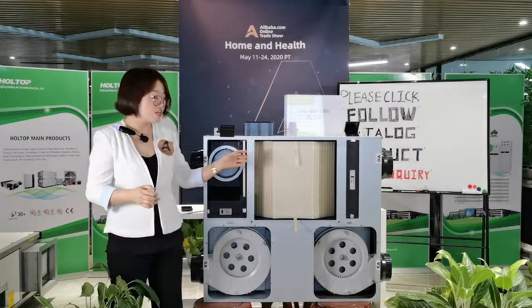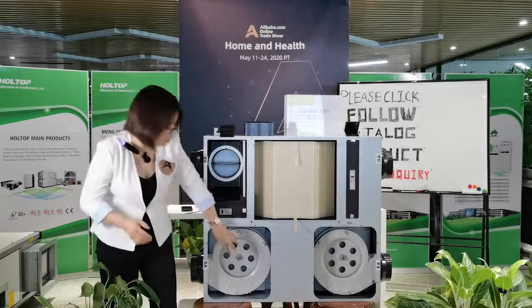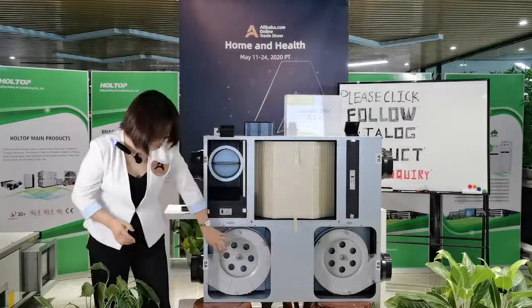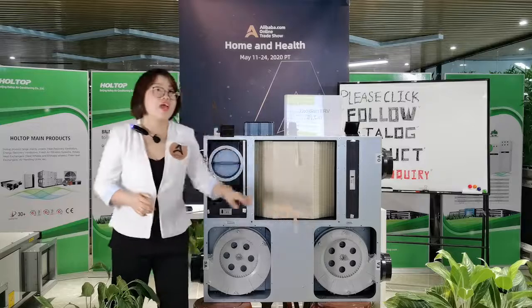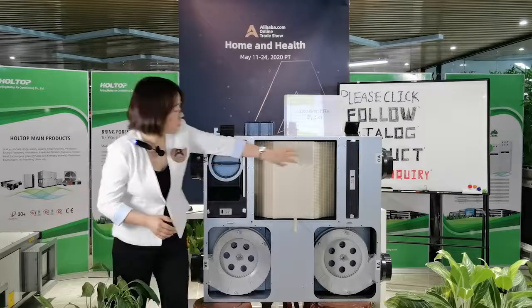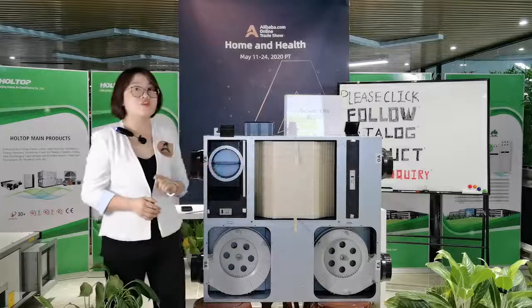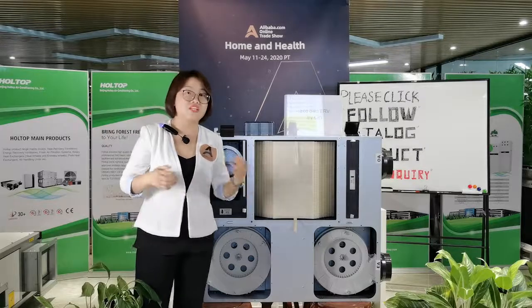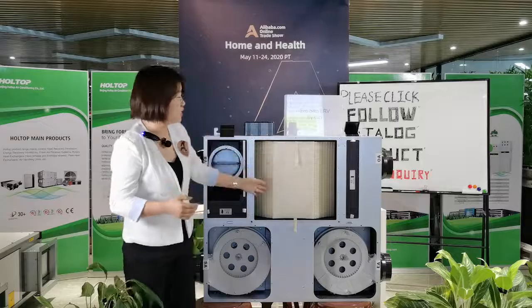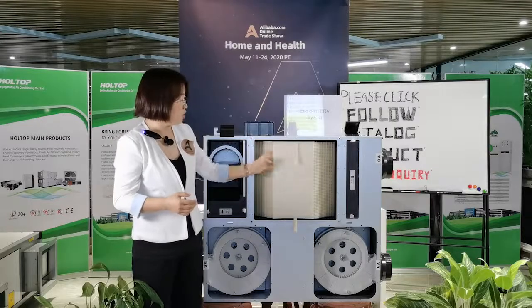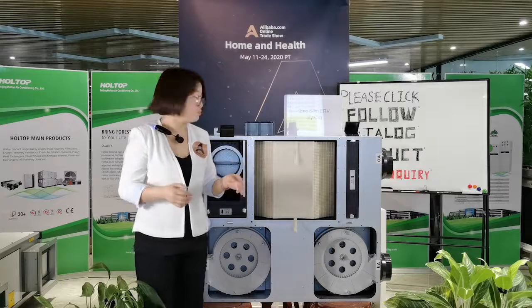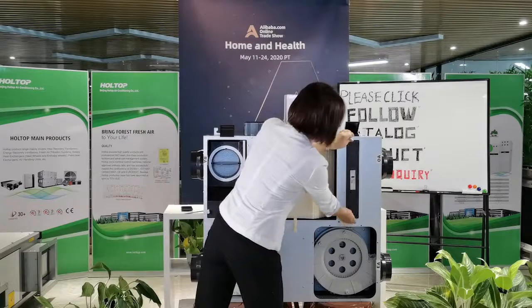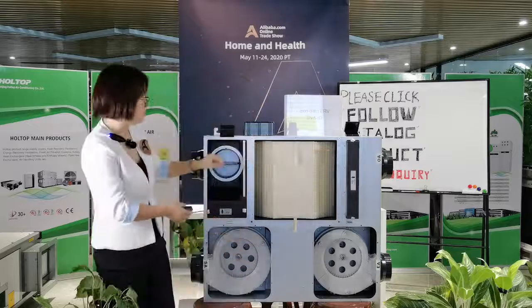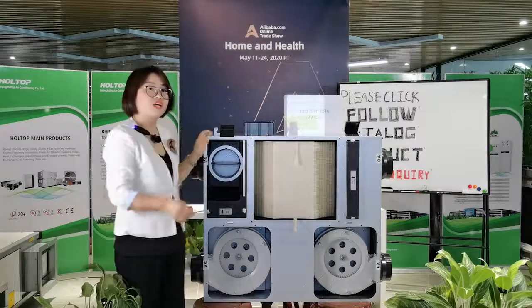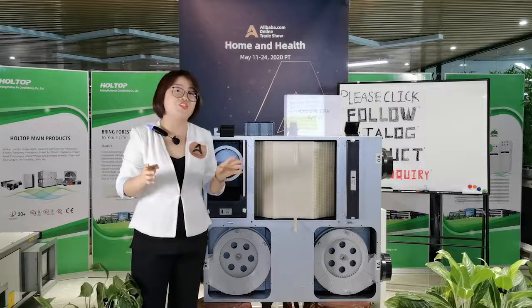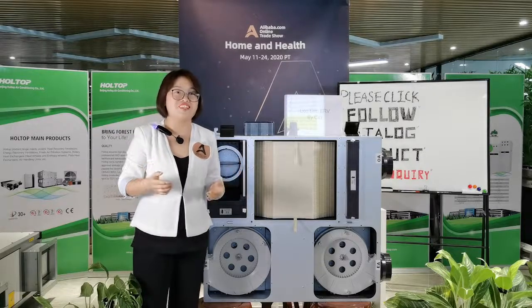There are two holes here for the fan motors, the supply fan and exhaust fan. The two holes here are mainly for primary filter and PM2.5 filter maintenance. The middle big hole is mainly for cross counterflow heat exchanger maintenance, and it's very easy to take the spare parts out. But please remember to cut off the power before maintenance.